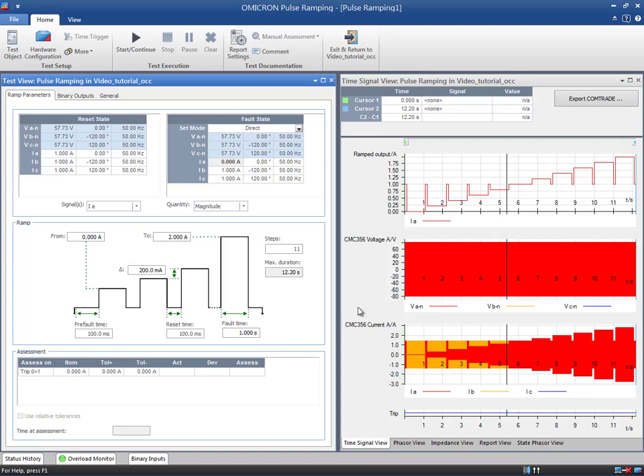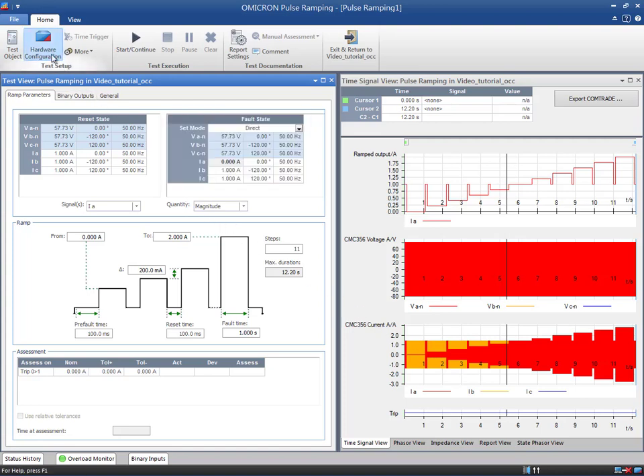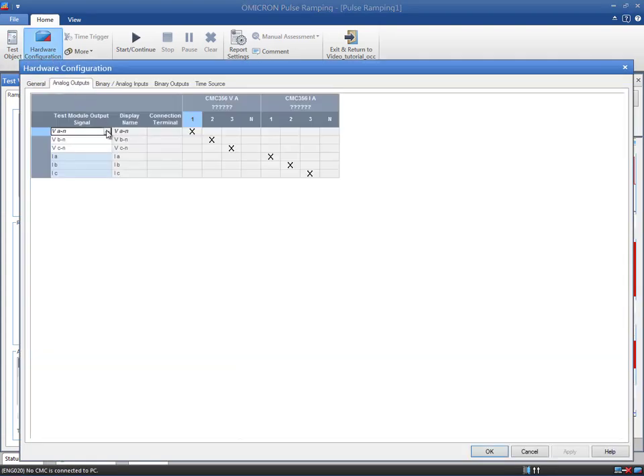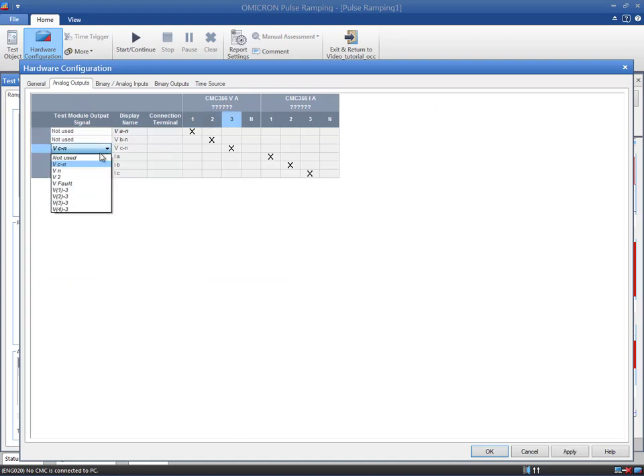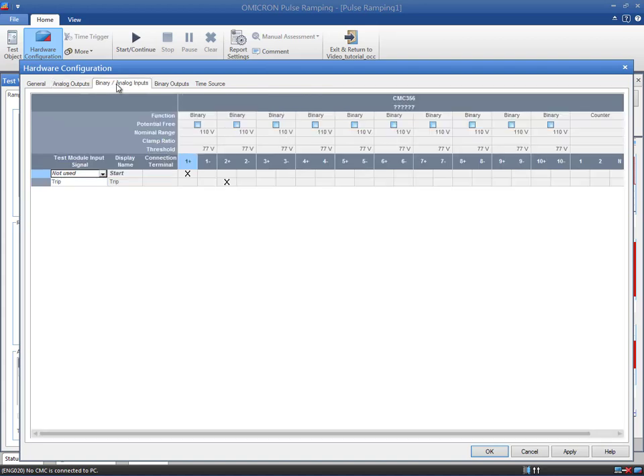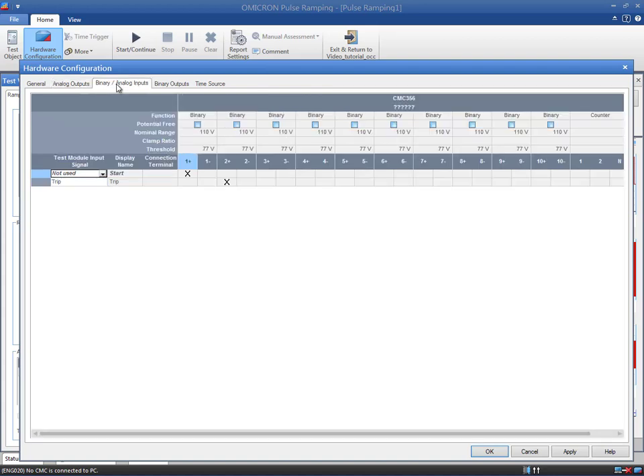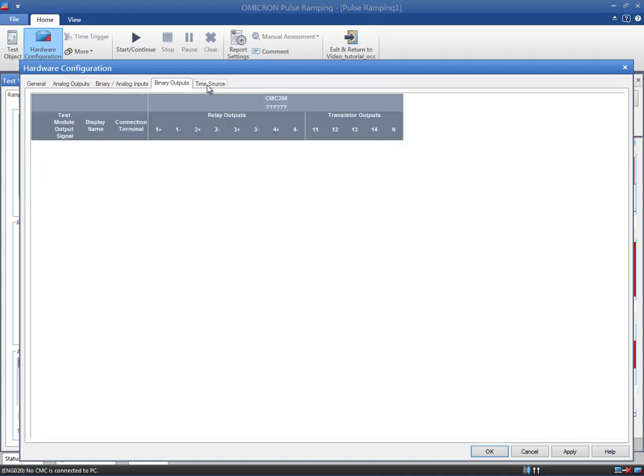Regarding the hardware configuration, we activate three currents and the trip contact. It is not possible to use the pickup contact because this signal will be active at any time after reaching the first element. None of the other signals are needed.